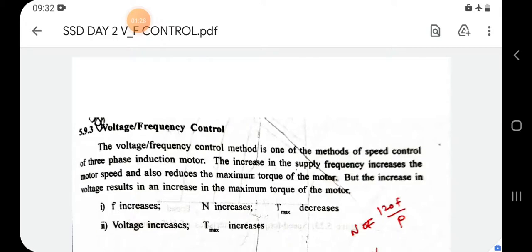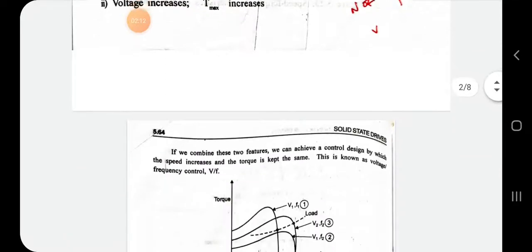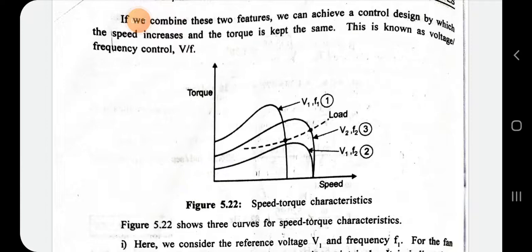From the torque expression, T is directly proportional to V² — that is from the stator voltage control we already derived that expression. So if we increase the voltage value, the torque value also increases. By combining these two features — frequency control and voltage control — we achieve a speed control method where speed increases but torque is kept the same, which is known as V/f control.